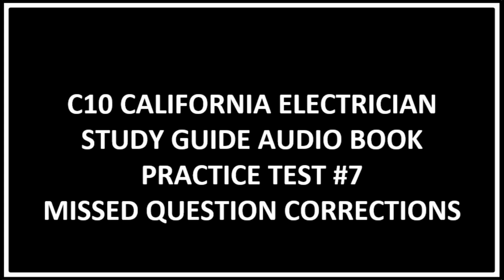Question 72. Utilization equipment on a circuit with other load, cannot exceed 50% load rating. Equipment installed on circuit with other loads, may not exceed 50%. Dedicated loads, 80%. Shared load, 50%.